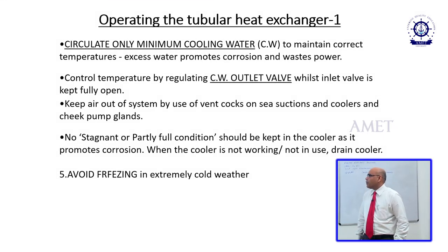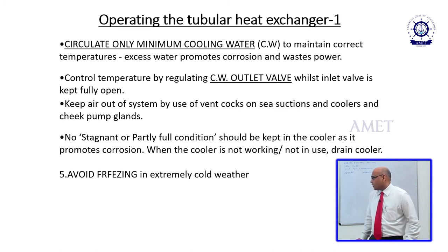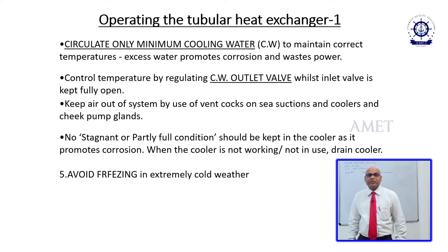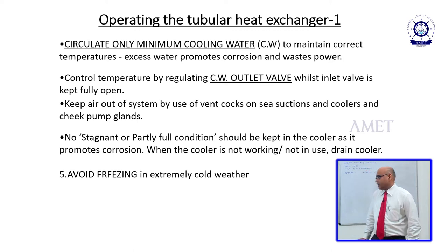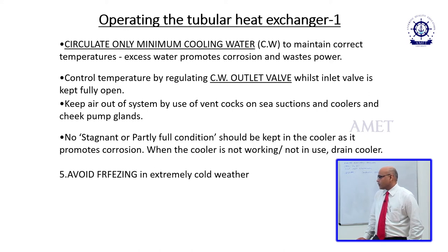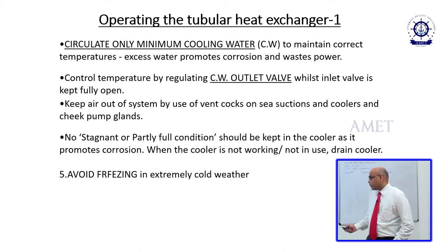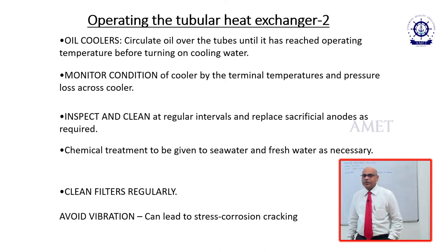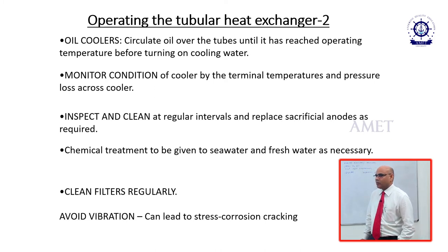When operating the shell-and-tube heat exchanger to maintain the correct temperature, always ensure minimum water is flowing — excess water promotes corrosion and wastes power. Control the temperature by regulating the outlet of the heat exchanger; never throttle the inlet. Keep air out of the system by venting properly, avoid freezing in cold weather, and regularly maintain the log to ensure temperature difference and pressure difference are monitored to identify the condition of the heat exchanger.